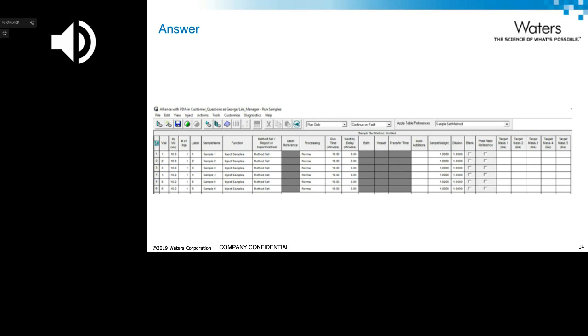And in the processing method, you can set a tolerance based on the reference standard. So if you want to take advantage of that, again, you would have to check the box to indicate which one in the Q is the reference standard. So if the ratio is 20 to 1, and we can set a 10% plus or minus on that, then you have to indicate which one is the reference. It compares it to the reference, and if it's within the tolerance, great. If it's outside of it, it would be a faulted result. Those values appear in red.